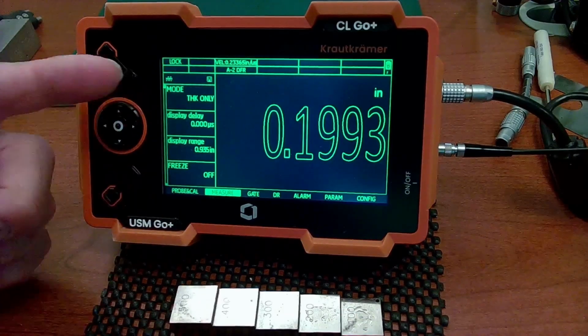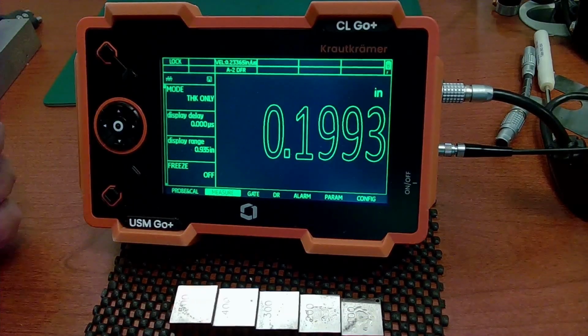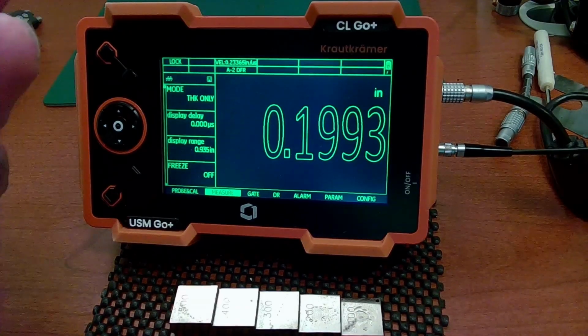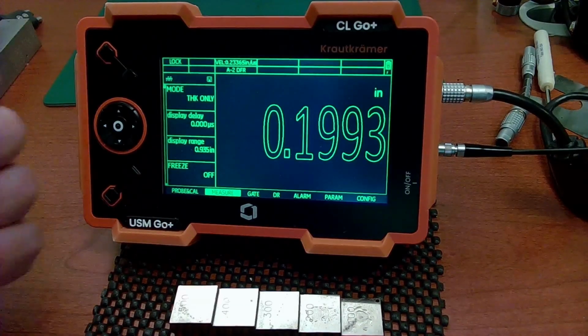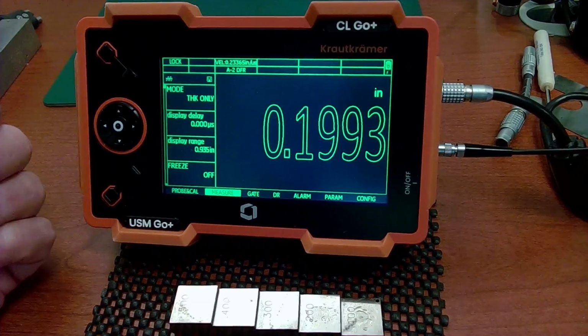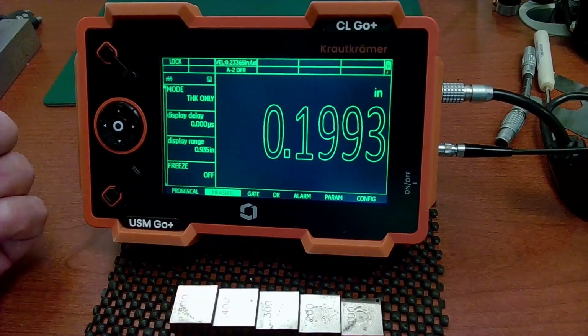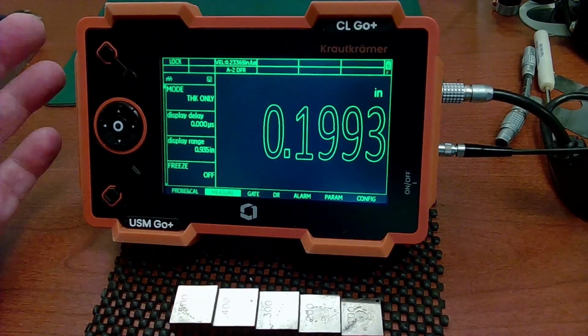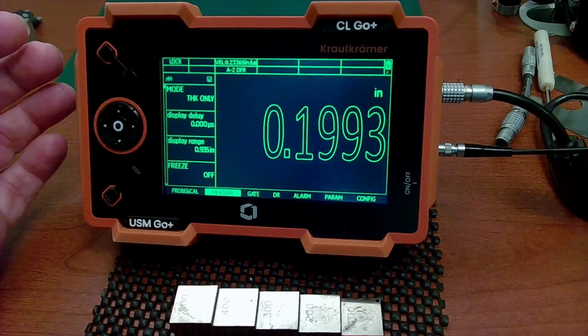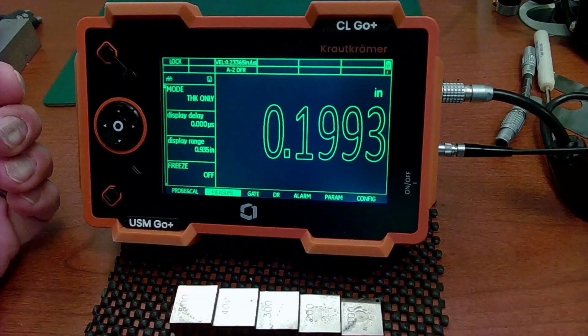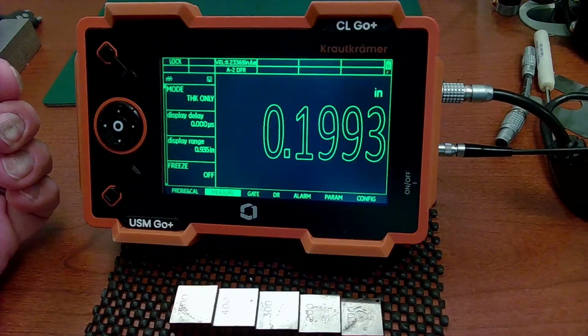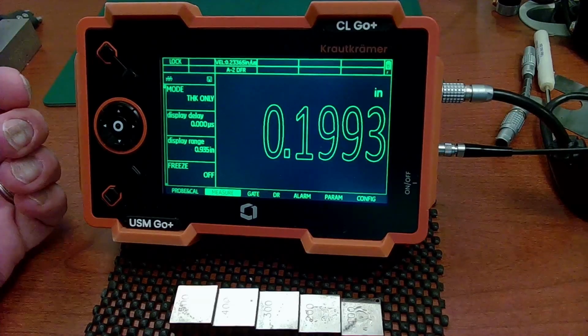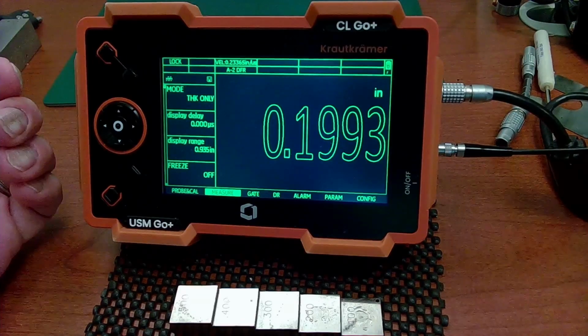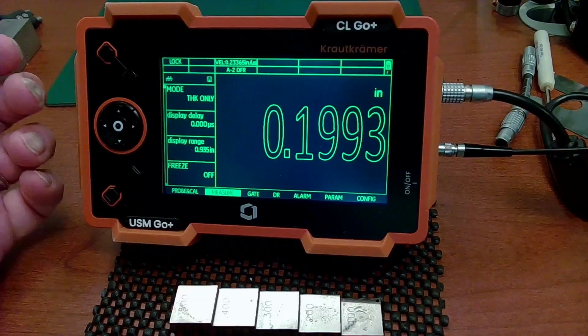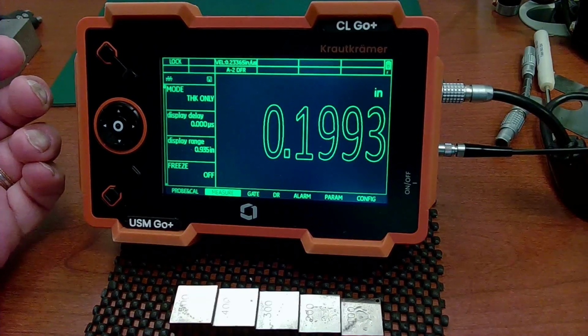For each probe that we support directly, we provide an initial setup where just selecting the probe and doing a calibration will work on most materials within the range of thickness of the probes, most of the time. There are certain situations, odd materials, oddly shaped parts, where you may have to make adjustments to gate positions, gains, and things like that. Those are things that take some skill to set up.